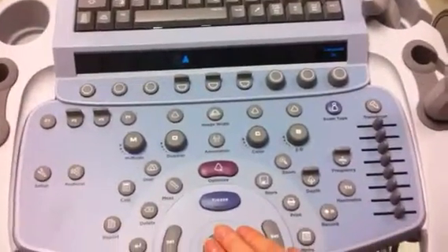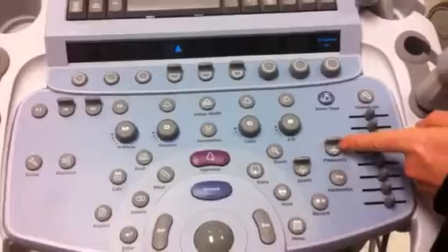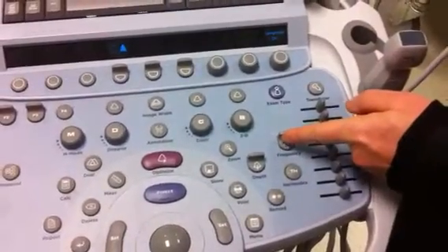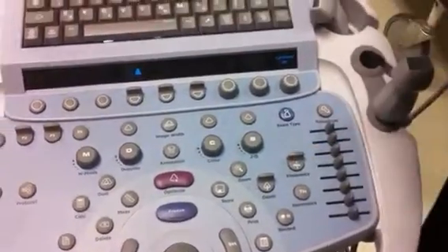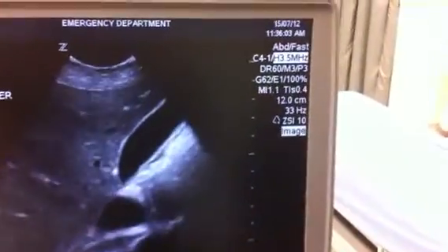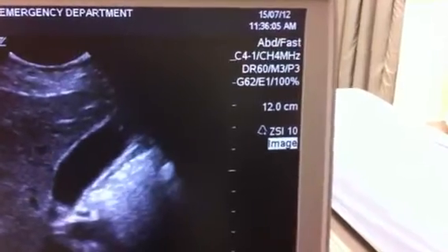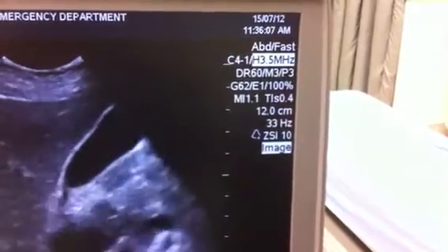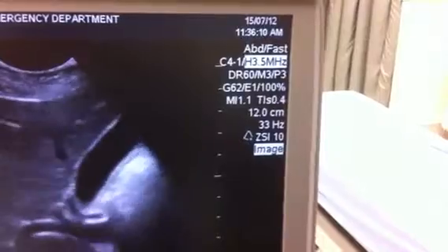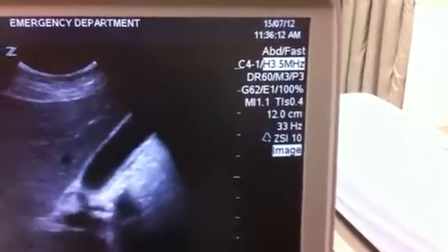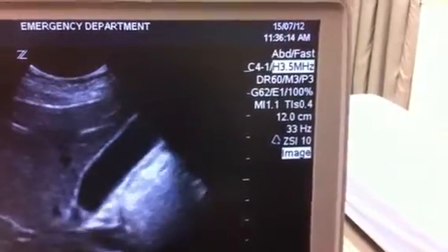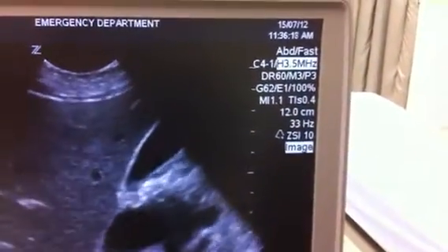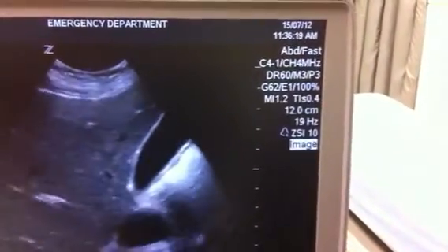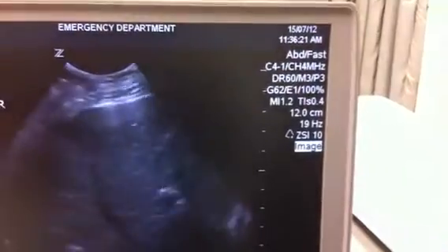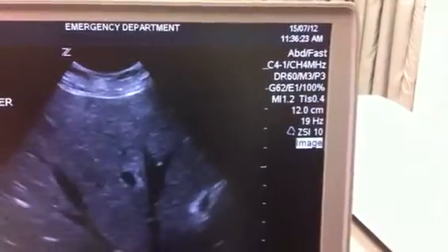If required, you may want to change the frequency. This is another toggle switch here. And it shows you on the screen the different frequencies you can select. The lower frequencies for greater penetration and the higher frequencies for better resolution. You can also use the software algorithms of harmonics to decrease artifact and compounding to increase resolution.